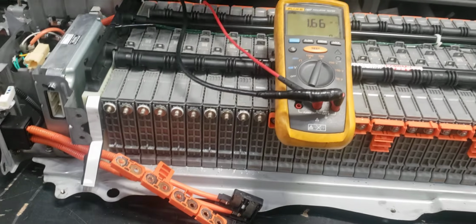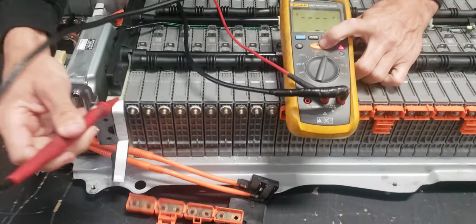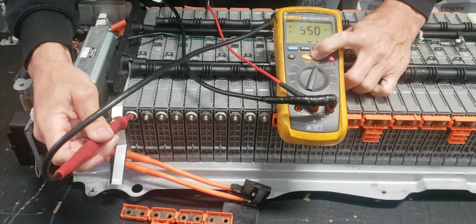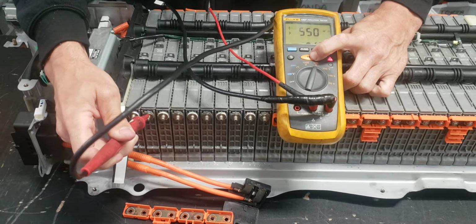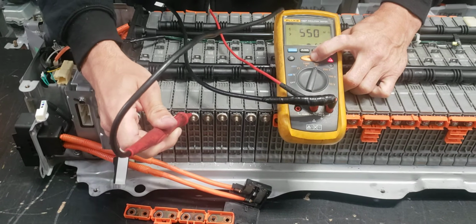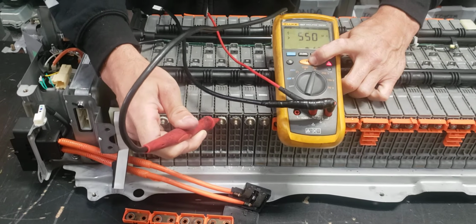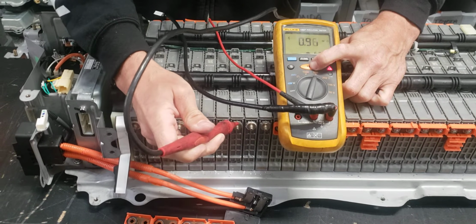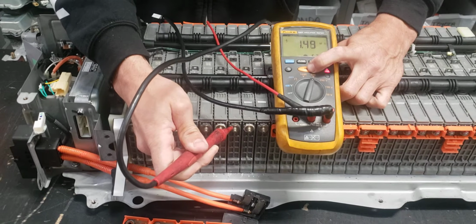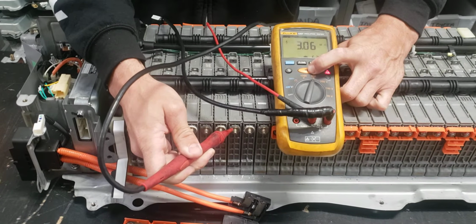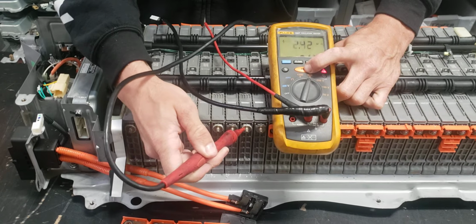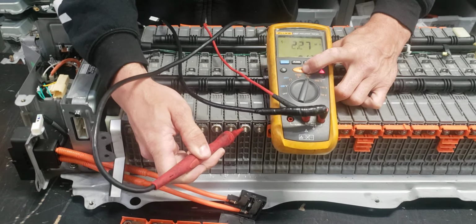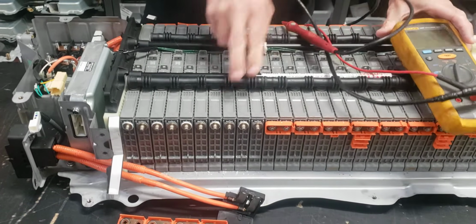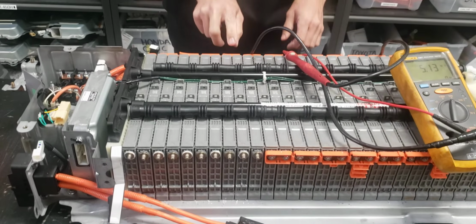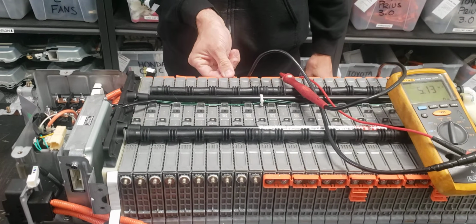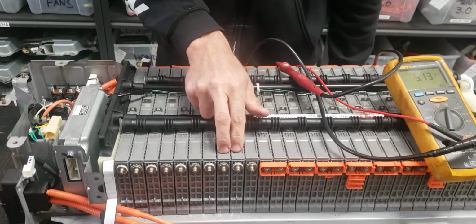Now we're just going to go cell by cell and see if we find an issue. Perfect, 550, same. There we go - and if you do the next cell, that cell is also appearing to be bad, but that's because if you follow these two cells here, they're connected with the bus bar over here. If you disconnect this bus bar, one of these is going to fail.